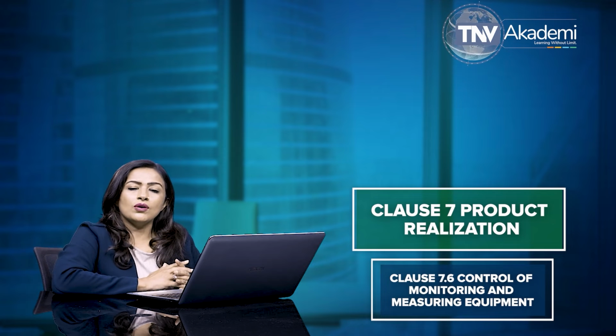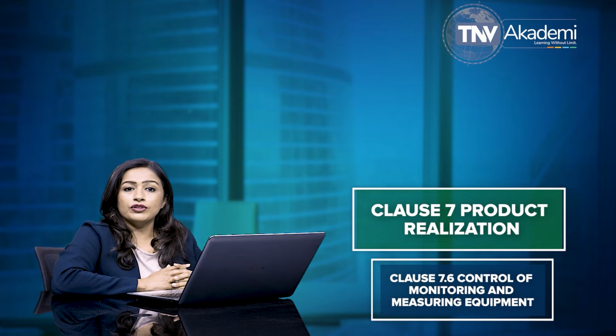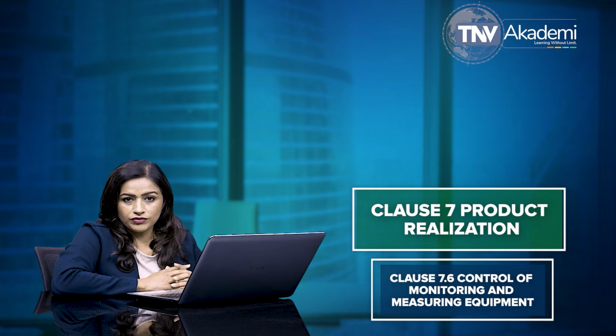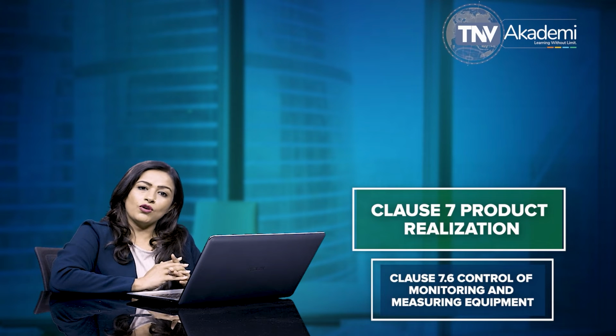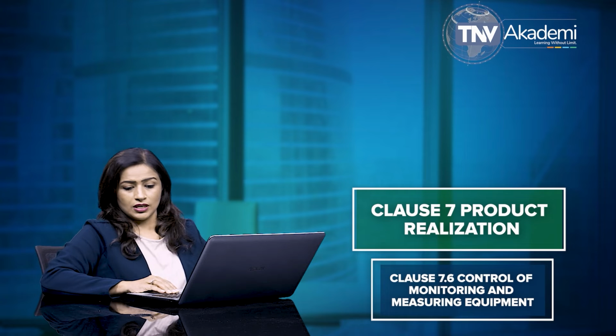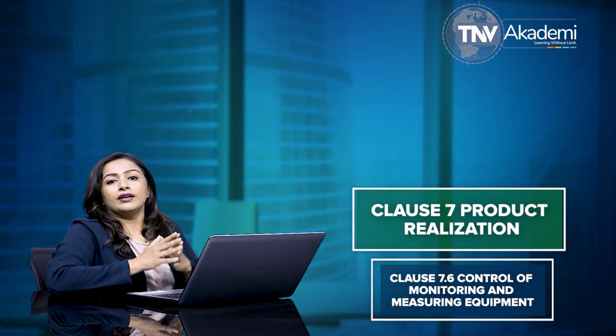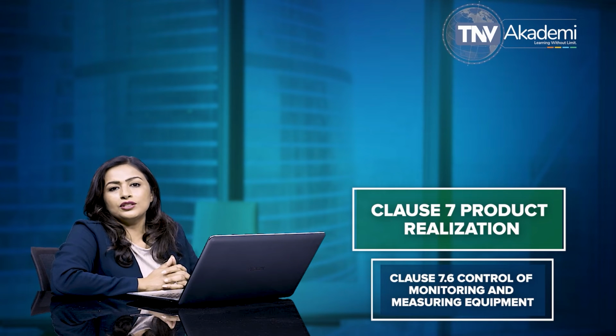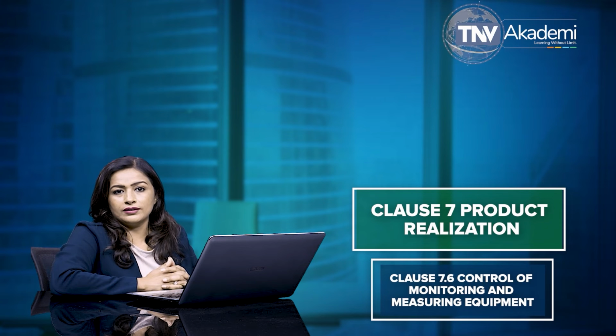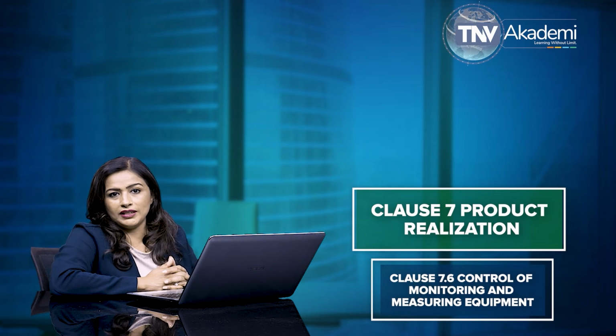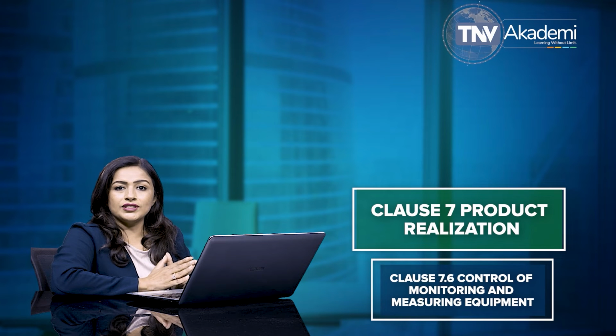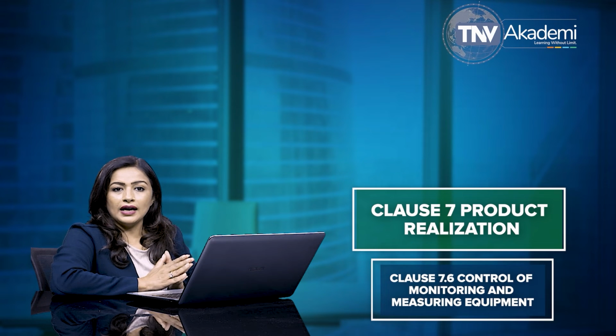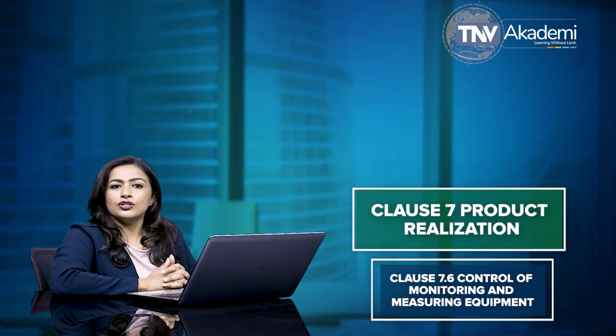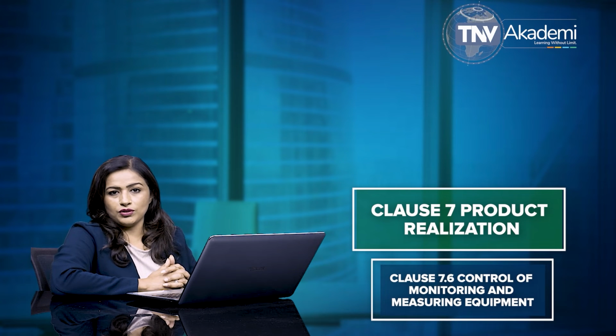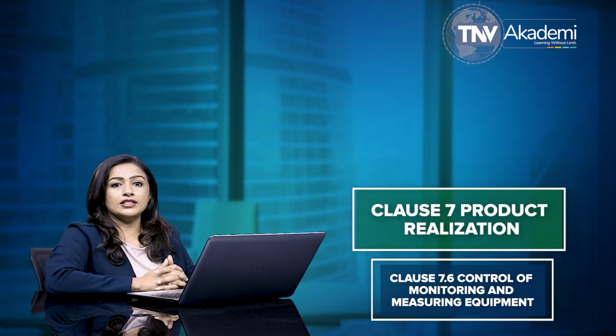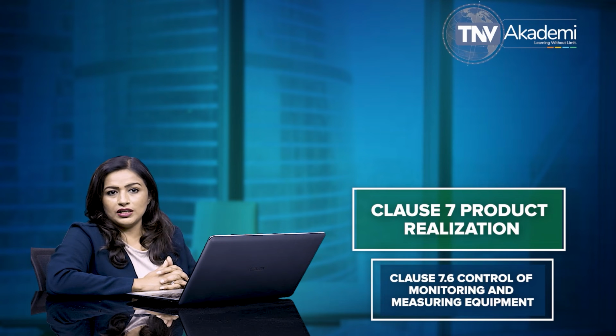According to this clause, the organization must document procedures for the validation of the application of computer software used for the monitoring and measurement of the requirements. As per the clause, such software applications are required to be validated prior to initial use and, as appropriate, after changes to such software or its application. The specific approach and activities associated with software validation and revalidation must be proportionate to the risk associated with the use of the software, including the effect on the ability of the product to conform to specifications.